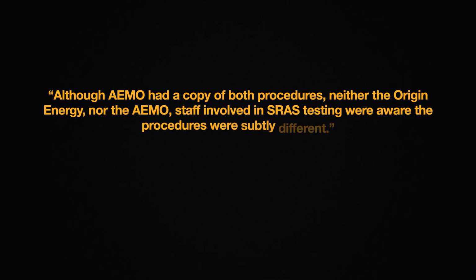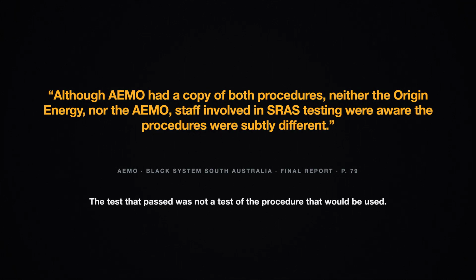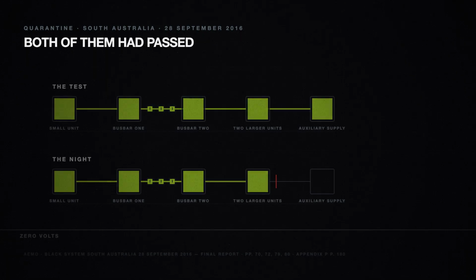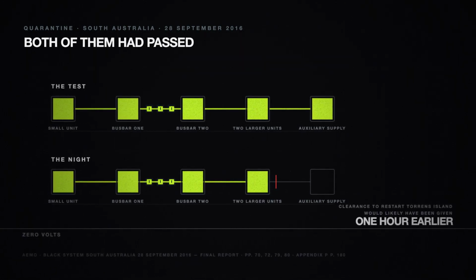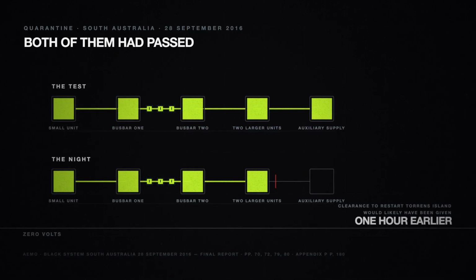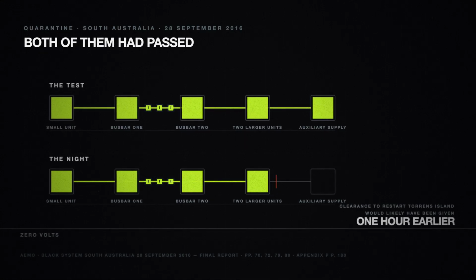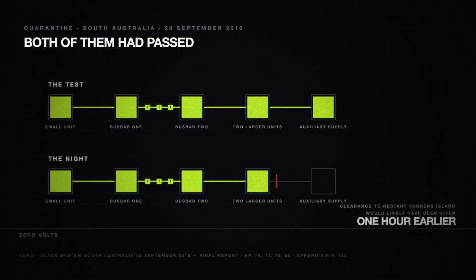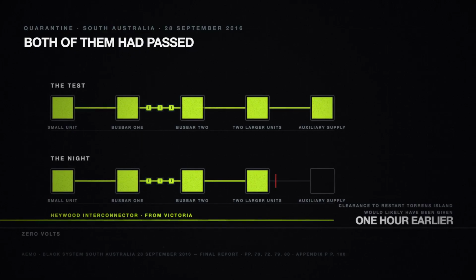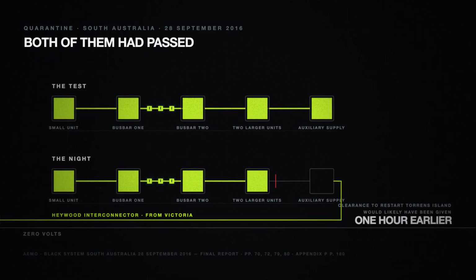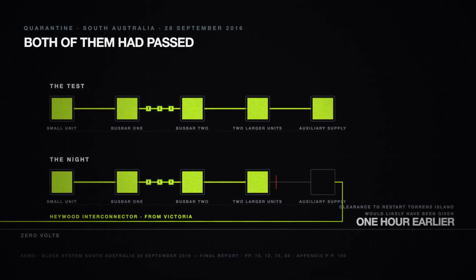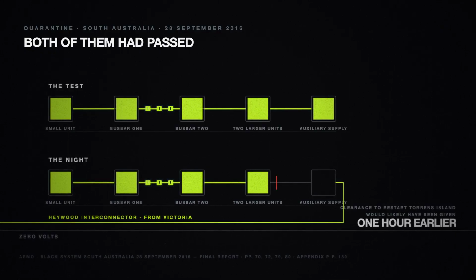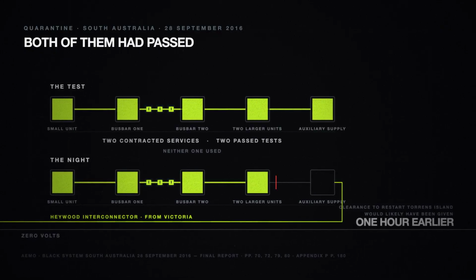The market operator's report records what nobody had noticed. Although it had a copy of both procedures, neither the generator's staff nor its own were aware the procedures were subtly different. The test that passed was not a test of the procedure that would be used. The cost, in the same report: clearance to restart the Torrens Island generating units would likely have been given approximately 1 hour earlier. What actually brought the state back was the Heywood interconnector from Victoria. The restart service's auxiliary supply was not completed before supply to the Torrens Island area arrived over it. 2 contracted services, 2 passed tests, neither one used.